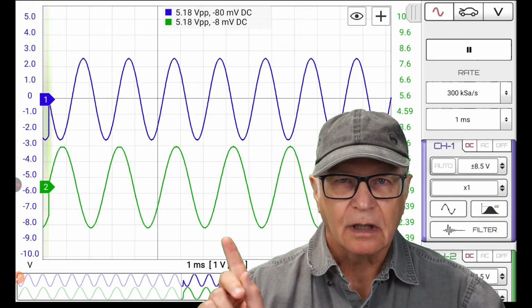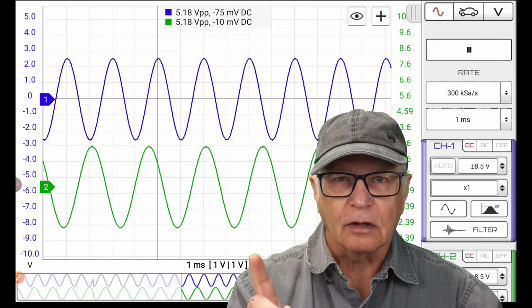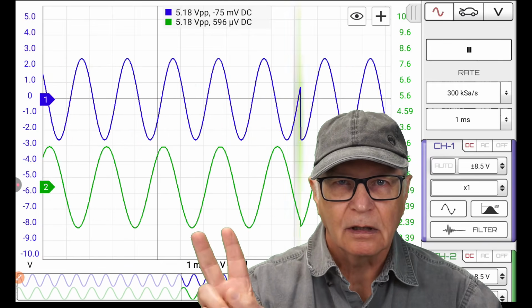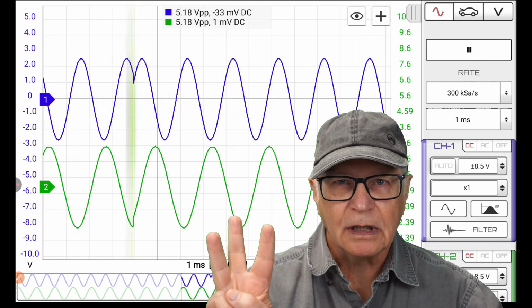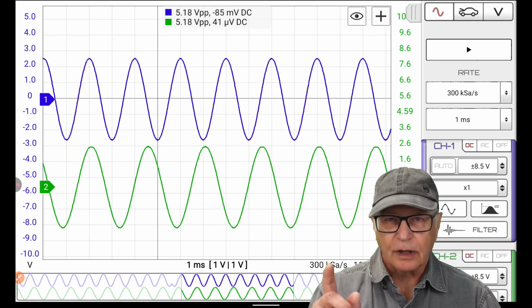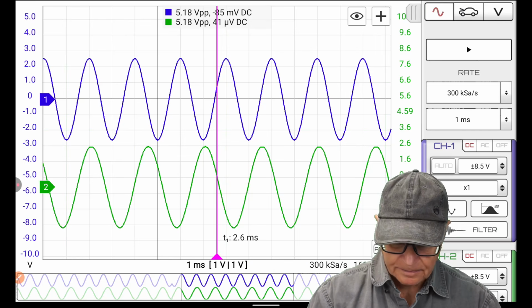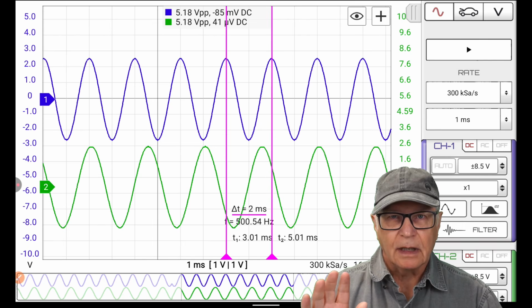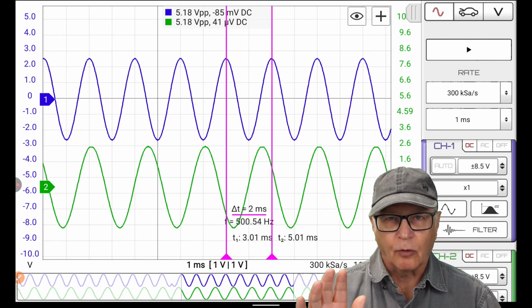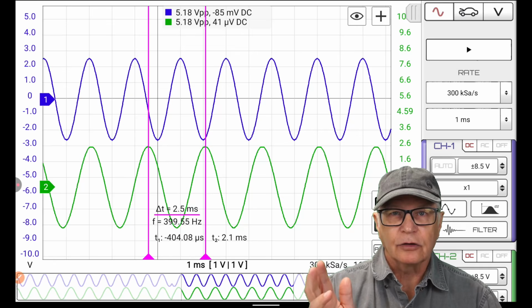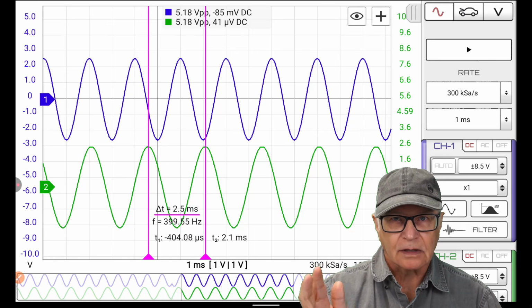We have two channels, each with their own sine wave. This tutorial will explore how these two channels can be viewed in three totally different ways. If I bring in two vertical cursors, in this view, it is very easy to measure that channel 1 has a 500 hertz sine wave, and that channel 2 has a 400 hertz sine wave.